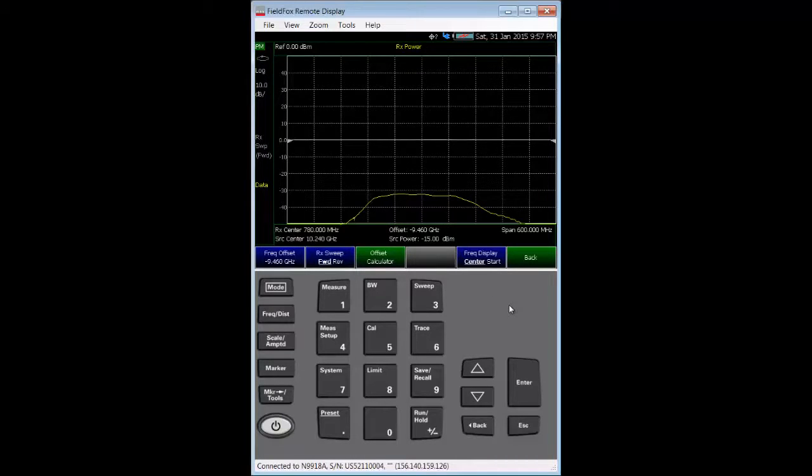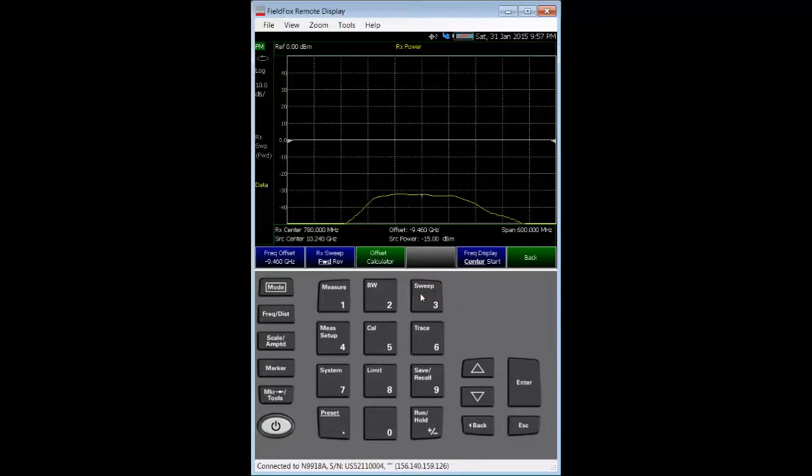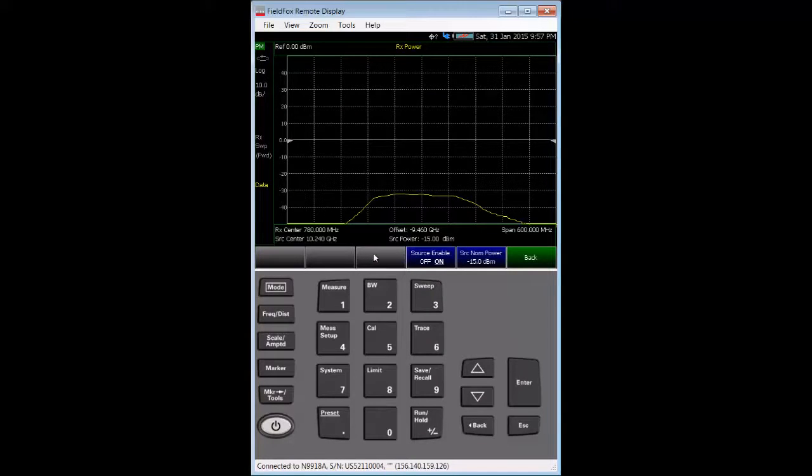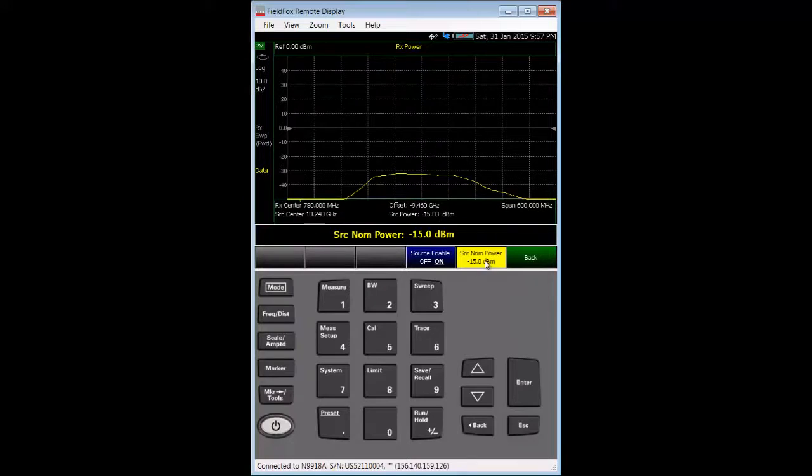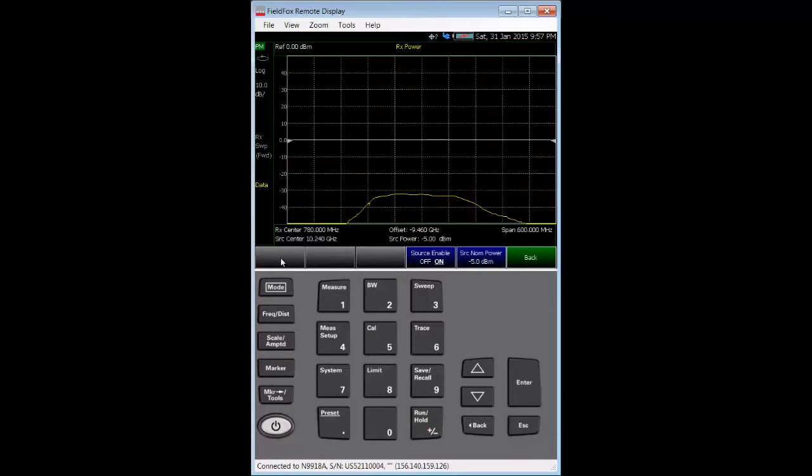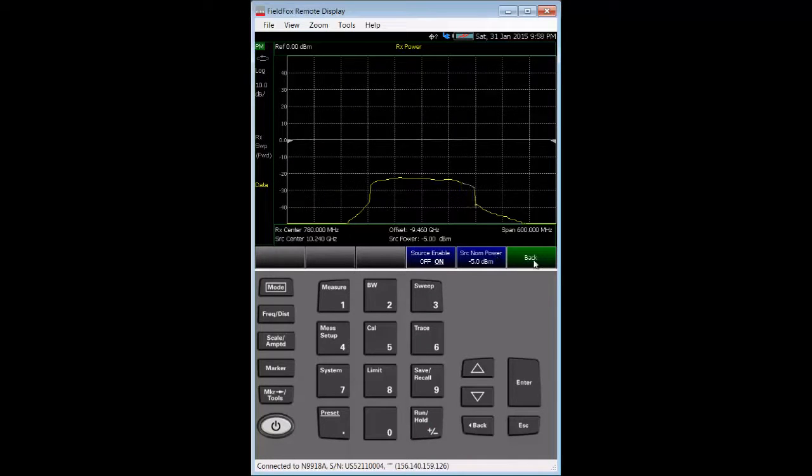Next, press the sweep hard key, and then select the power setup soft key. Note that the source is enabled, and we'll set the source nominal power to minus 5 dBm. With that entered, we then press the back soft key.